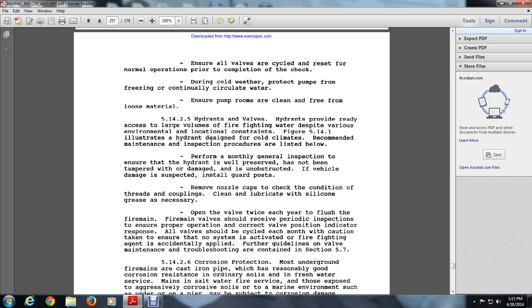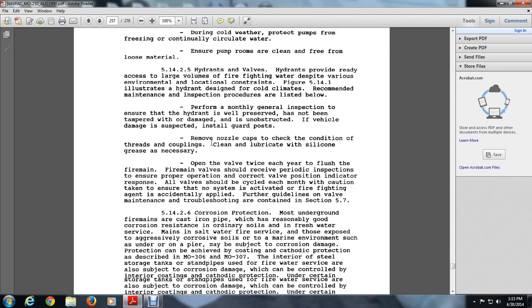Flush the hydrants. The firemain valves should receive periodic inspection to ensure proper operation and the correct valve position indicator response. All valves should be cycled each month, and caution taken to ensure no system is activated by firefighting agent accidentally applied. For further guidance on valve maintenance, troubleshooting, and containment, see 5.7.